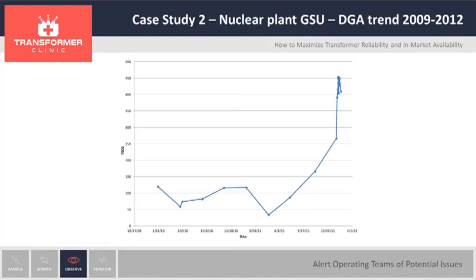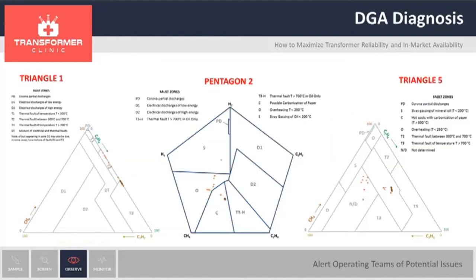The second case is a much bigger transformer — a GSU transformer for a nuclear plant. Here you can see the DGA data. For several months, the DGA was relatively stable. However, by the end of 2011, the gas had increased. When looking at the DGA data and applying the Duval Triangle and Pentagon, Triangle 1 gave us a diagnosis moving from T2 all the way to T3, a high temperature fault. If we look at Triangle 5, we started on a non-determined fault and then moved to carbonization. And with the Pentagon, we started with overheating and then moved to carbonization as well.